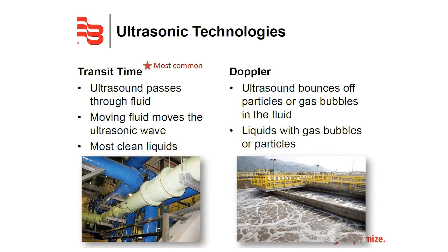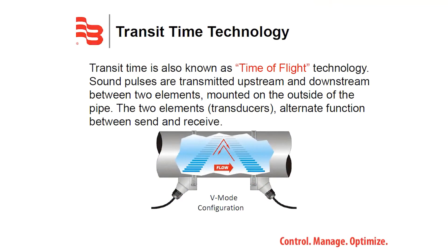There are two main types of ultrasonic flow meters: transit time ultrasonics, designed specifically for cleaner liquids, and Doppler ultrasonics, designed for liquids that contain suspended solids. Transit time technology is the most common ultrasonic technology, utilizing transducers for cleaner applications, also known as time of flight.